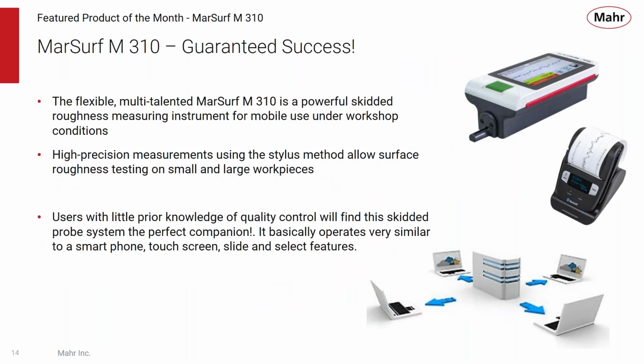With the M310, I think you're going to get guaranteed success. It's a flexible, multi-talented, skidded roughness measuring instrument that can be used at the point of manufacture under workshop conditions. It provides high precision measurements using a stylus method that allow for surface roughness testing on small and large workpieces. You can fixture a small workpiece to the gauge, or you can bring the M310 to a larger part. And the nice thing about the M310 is that users with little prior knowledge of quality control or surface finish will find this skidded probe system the perfect companion.